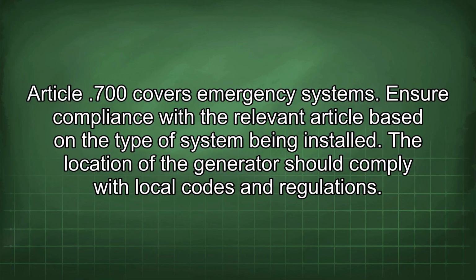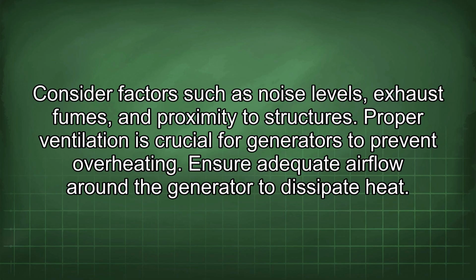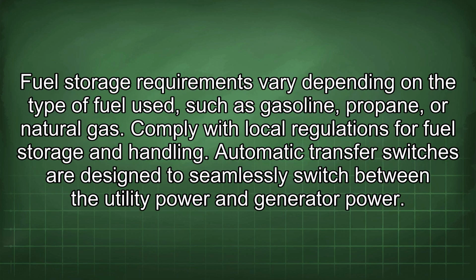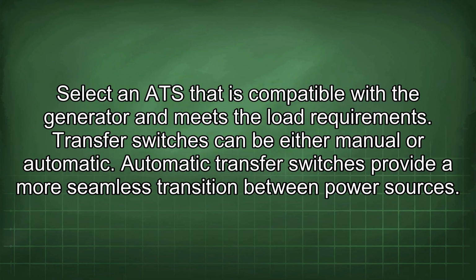The location of the generator should comply with local codes and regulations. Consider factors such as noise levels, exhaust fumes, and proximity to structures. Proper ventilation is crucial for generators to prevent overheating. Ensure adequate airflow around the generator to dissipate heat. Fuel storage requirements vary depending on the type of fuel used, such as gasoline, propane, or natural gas. Comply with local regulations for fuel storage and handling. Automatic transfer switches are designed to seamlessly switch between the utility power and generator power. Select an ATS that is compatible with the generator and meets the load requirement.